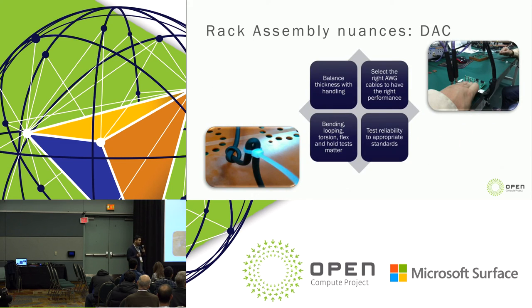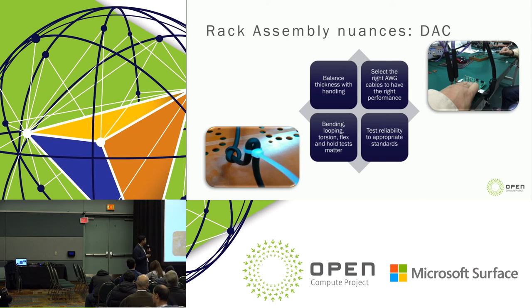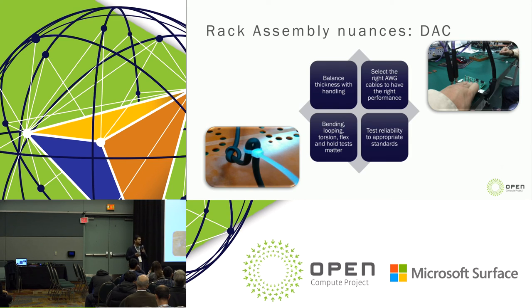Key takeaways when thinking about DACs: balance cable thickness with handling requirements at the rack level; select the right gauge cables to meet signal integrity performance requirements; bending, looping, torsion, and flex tests actually matter, so encourage your vendors to do that; and test reliability to the appropriate standards — pick standards suited to your needs and have vendors execute them.